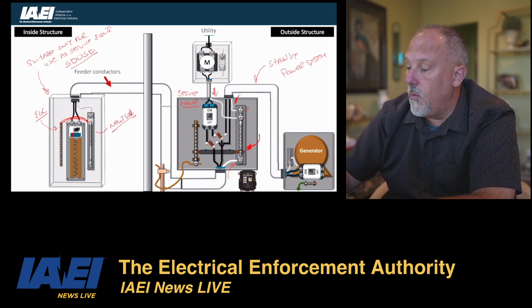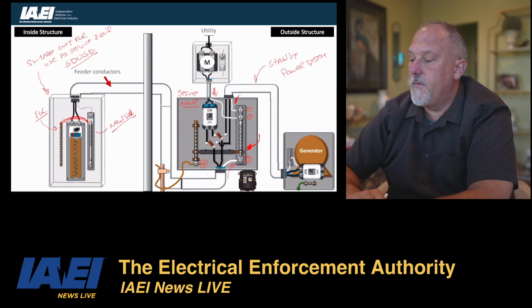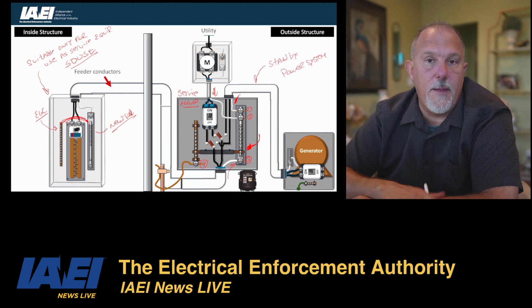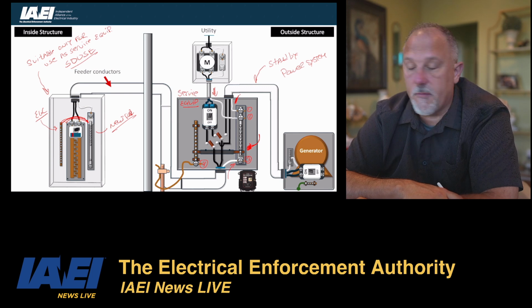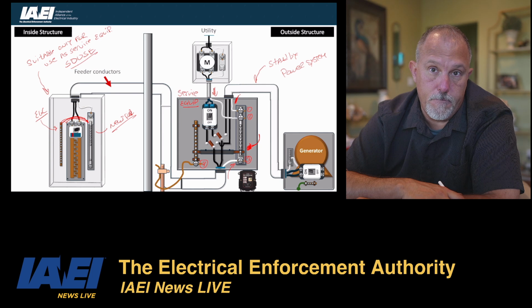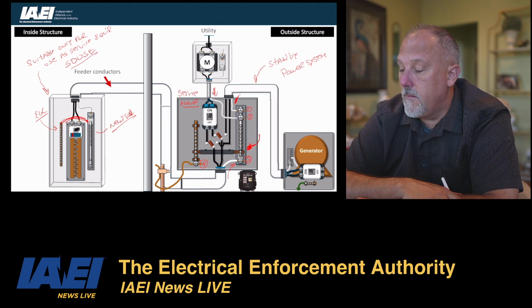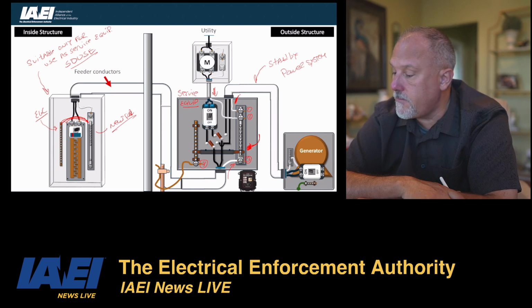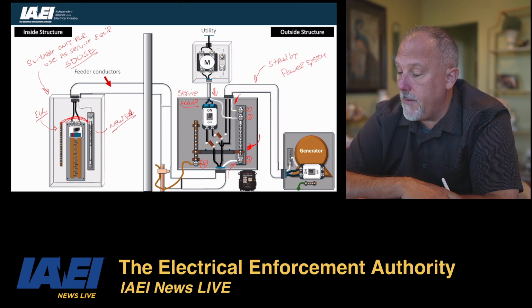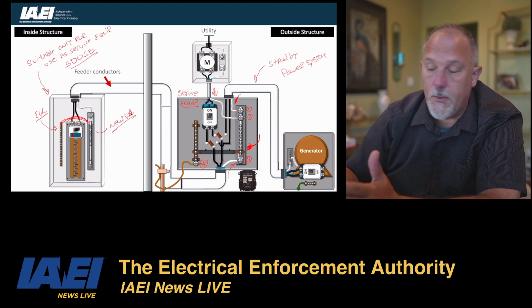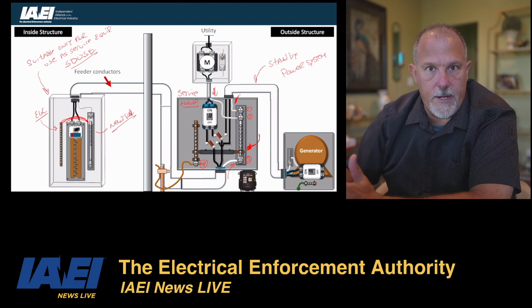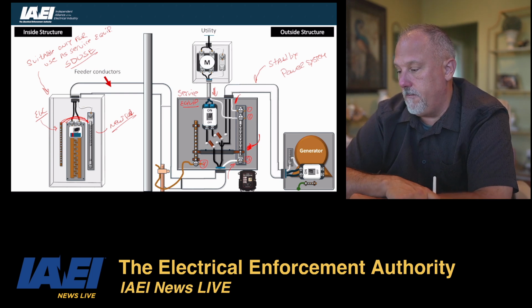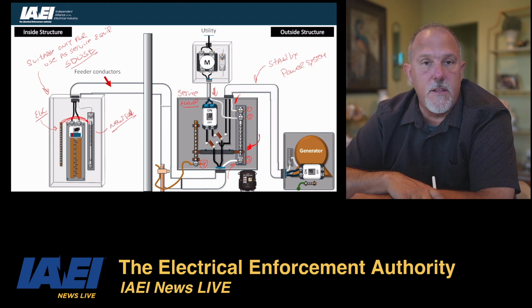You would need 1, 2, 3, and then 4, a total of 4 lugs to be able to handle the 3 neutrals and the EGC, or the 3 grounded conductors and the equipment grounding conductor, or the grounding electrode conductor, the GEC. And then obviously, because that neutral bar and the ground bar are bonded together, because it's service rated equipment, you're good to go. Okay, so now that's a lot to take in.